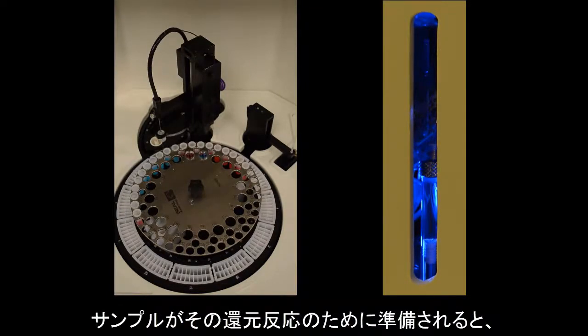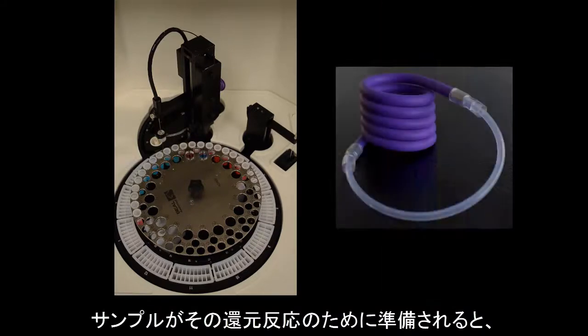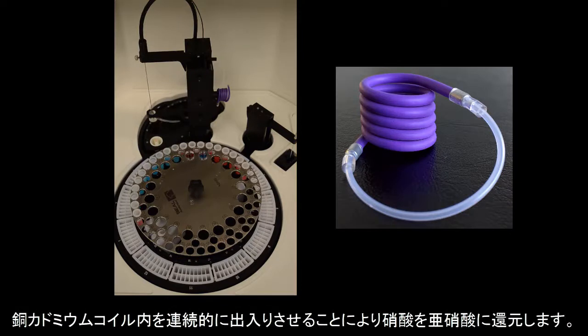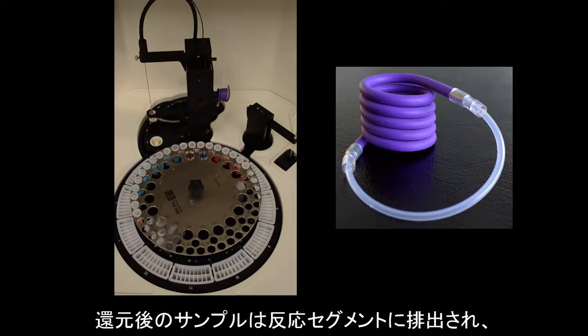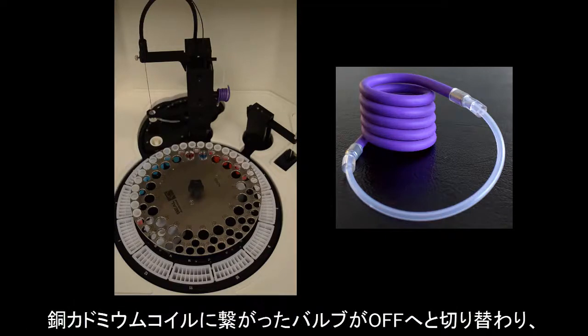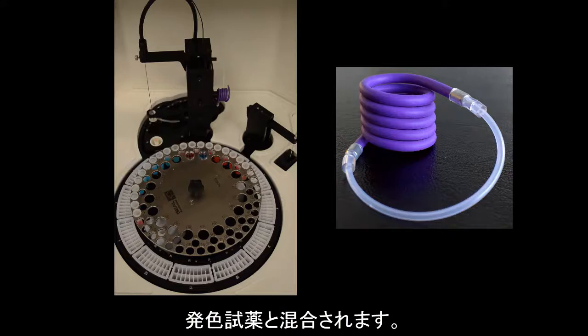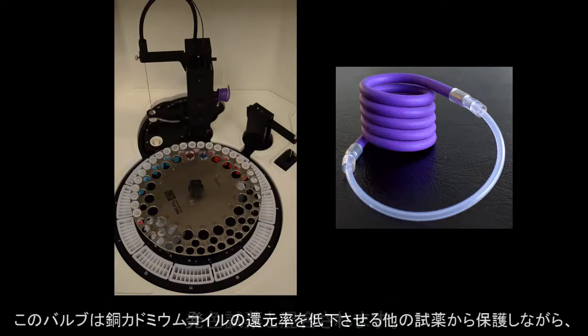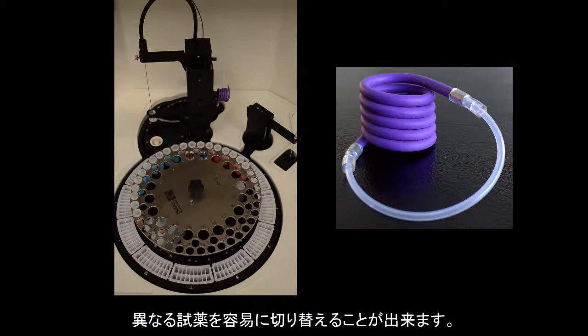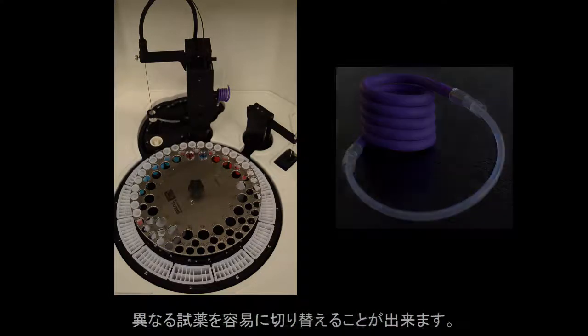When a sample is ready for the reduction step, the sample is pulled into the cadmium coil and the sample is sloshed back and forth in the coil to reduce the nitrate to nitrite. The reduced sample is then dispensed into a reaction well and the cadmium switching valve closes again before the color reagent is added to the sample. This valve allows the AQ400 to easily switch between different chemistries while protecting the cadmium coil from other reagents that may lower its reduction efficiency.